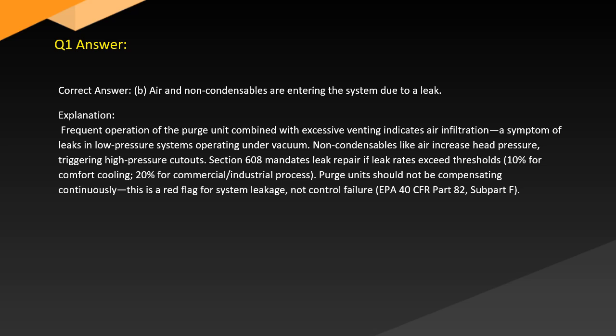Explanation. Frequent operation of the purge unit combined with excessive venting indicates air infiltration, a symptom of leaks in low-pressure systems operating under vacuum. Non-condensables like air increase head pressure, triggering high-pressure cutouts. Section 608 mandates leak repair if leak rates exceed thresholds, 10% for comfort cooling, and a different percentage for commercial and industrial process. Purge units should not be compensating continuously. This is a red flag for system leakage, not control failure. EPA 40 CFR Part 82 Subpart F.